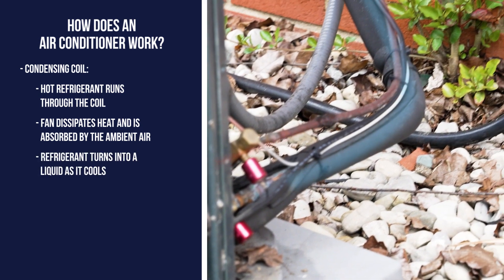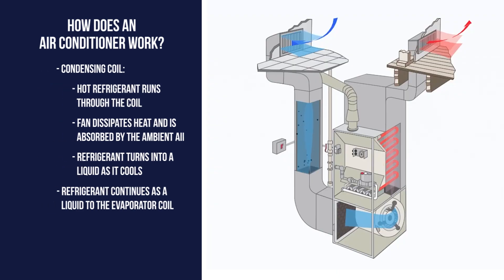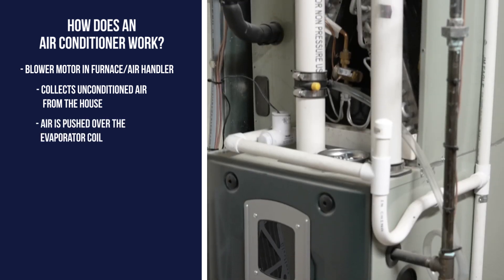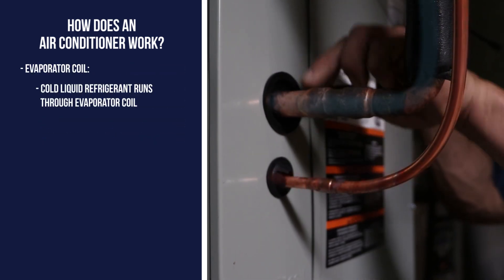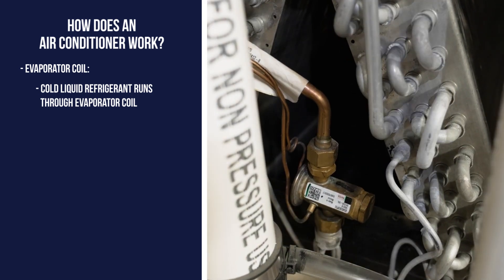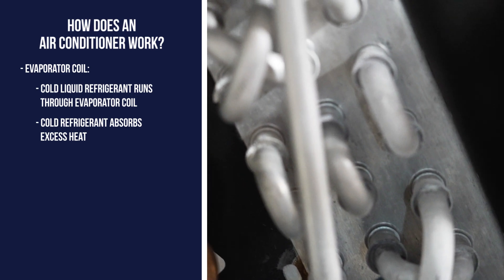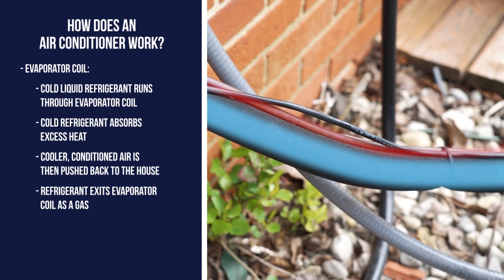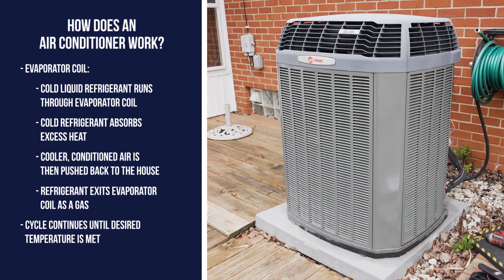As the refrigerant cools, it goes from a hot gas to a liquid and travels through the liquid line to the evaporator coil inside your home. Inside, the blower in your furnace or air handler has been collecting the hot, unconditioned air throughout the house via the return air ducts. The air is then pushed over the evaporator coil located above the furnace. As the refrigerant travels through the liquid line from the condenser through the evaporator coil, the temperature is much cooler than the air blowing over it. During this phase, the refrigerant absorbs this excess heat in the air while the conditioned, cooler air continues to blow throughout the rest of the house. By the time the refrigerant exits the evaporator coil, the liquid has evaporated back into a gas state where it continues its cycle.